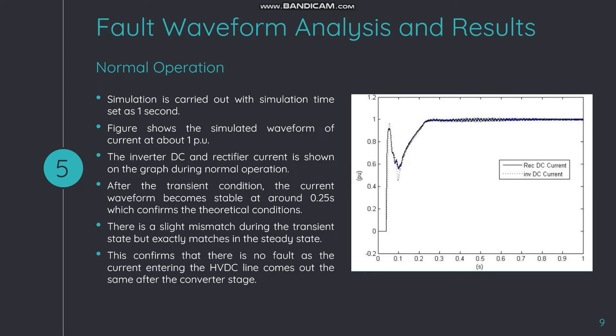Now for the results and waveform analysis: this figure shows the normal operation of the HVDC system. The simulation is carried out with a simulation time set to one second. The inverter DC and rectifier current are shown on the graph during normal operation. After the transient condition, the current waveform becomes stable at around 0.25 seconds. There is a slight mismatch during the transient state, but in steady state it exactly matches, confirming there is no fault as the current entering the HVDC line comes out the same after the converter stage.